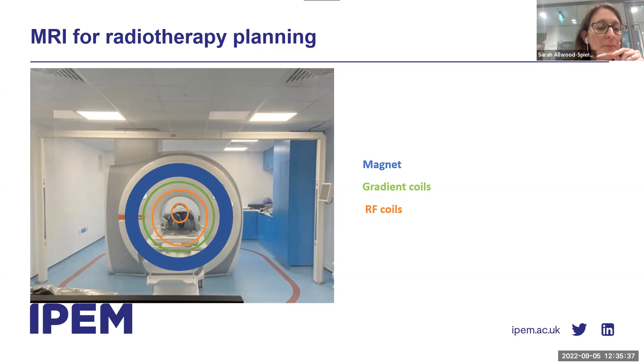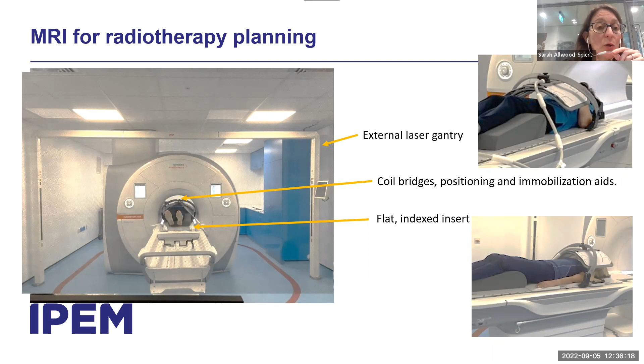A scanner for radiotherapy planning may also have a separate gantry for the laser for lining up your patient to their tattoos or markers. You may have a flat indexed insert for the table, coil bridges to position the coils close to the patient without resting them on the patient so that you're not changing the patient contours. You'll also have positioning aids and possibly immobilization to get the patient set up in the treatment position. And this may include putting their arms above their head. So suddenly the 70 centimeters doesn't look quite so generous.